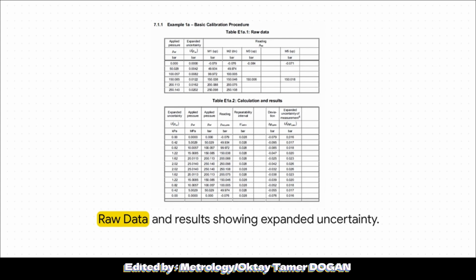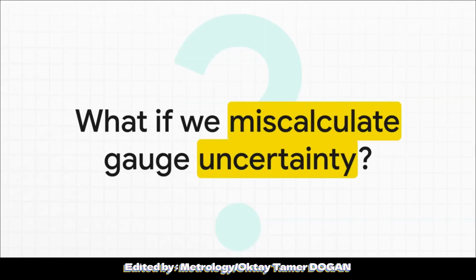When you actually run the numbers, you get real-world readings. Laboratories track the applied reference pressure, and then they log the actual readings taken from the test gauge as the pressure goes up and then comes back down. Using those formulas we just talked about, the lab calculates the deviation and applies an expanded uncertainty value. That final value proves exactly how far off the gauge might be at any given point on its dial. It's just incredibly precise. Which brings us to the ultimate so what.